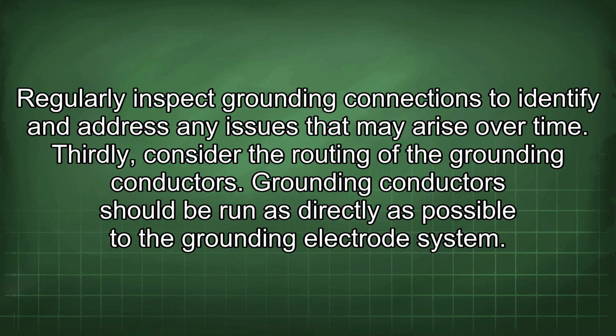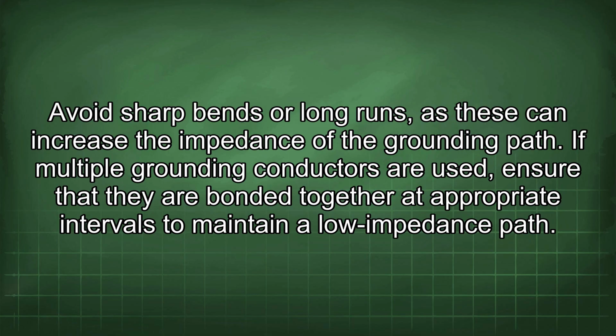Regularly inspect grounding connections to identify and address any issues that may arise over time. Thirdly, consider the routing of the grounding conductors. Grounding conductors should be run as directly as possible to the grounding electrode system. Avoid sharp bends or long runs, as these can increase the impedance of the grounding path. If multiple grounding conductors are used, ensure that they are bonded together at appropriate intervals to maintain a low impedance path.